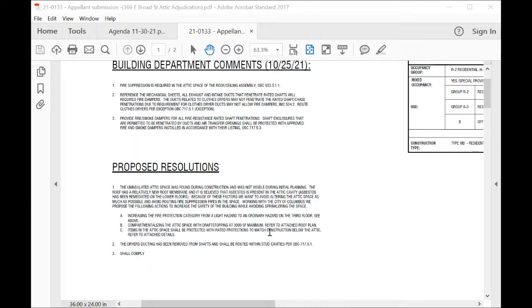It's a short enough building that the fire department can ladder it from an aerial truck without having to go on the roof if necessary. There's a standpipe, and the area where there most likely would be a fire is in the mechanical or elevator space. Frankly, fire department access is tight. I could support a variance with just the conditions we've outlined so far, without the detection system.